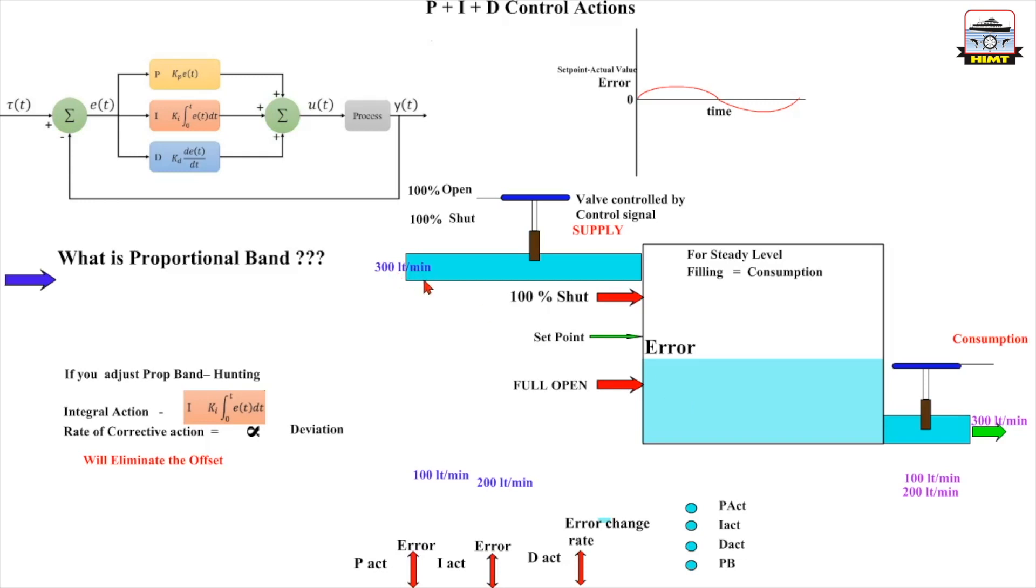So the valve will continue to open because the error is there. And if the valve continues to open more than what was required, that 300 liters per minute, the level will start rising up and it will remove the deviation. You see, this is the job of the integral action.